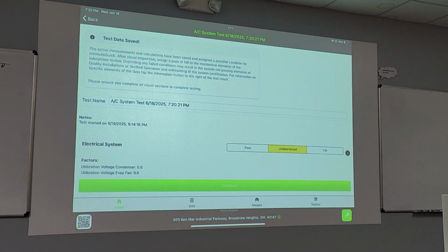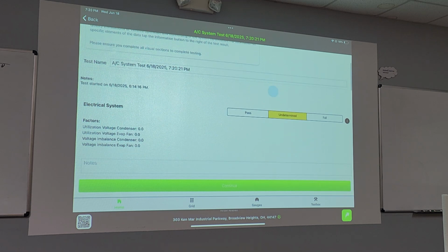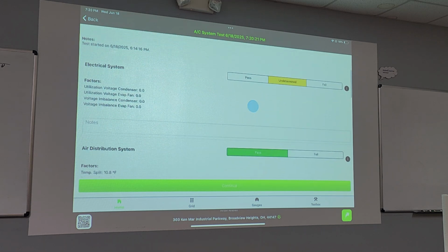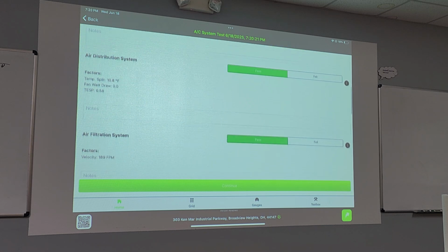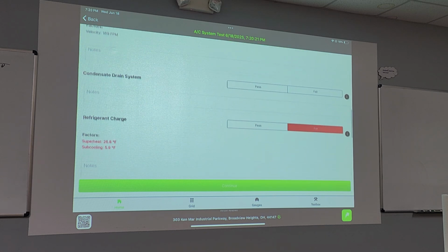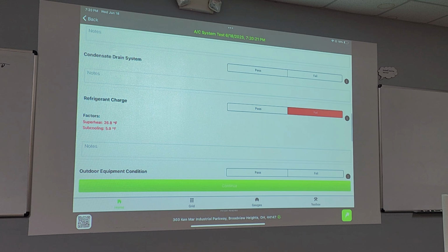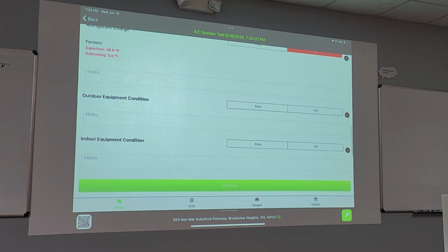The first thing it takes me to is the subsystem review. Most of these categories are set based on measurements taken with the probes, but a few aren't—I can't measure the performance of the condensate drain, so I have to manually confirm that the drain is intact and flowing.